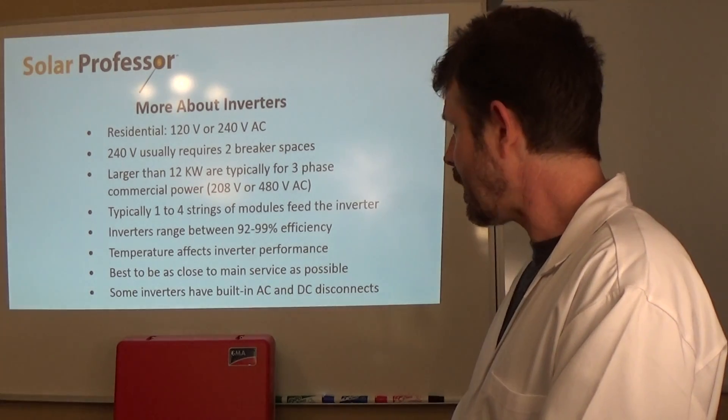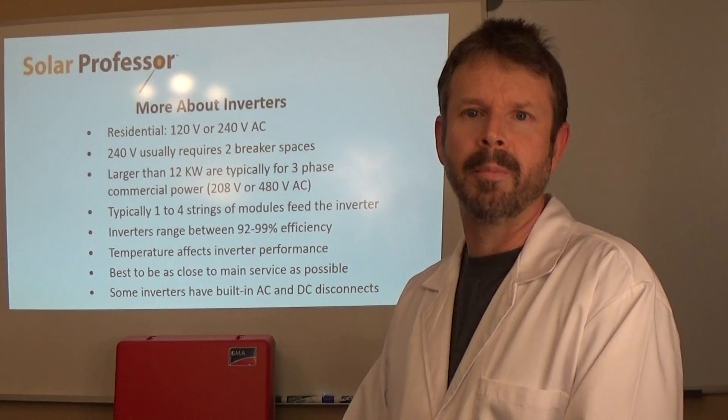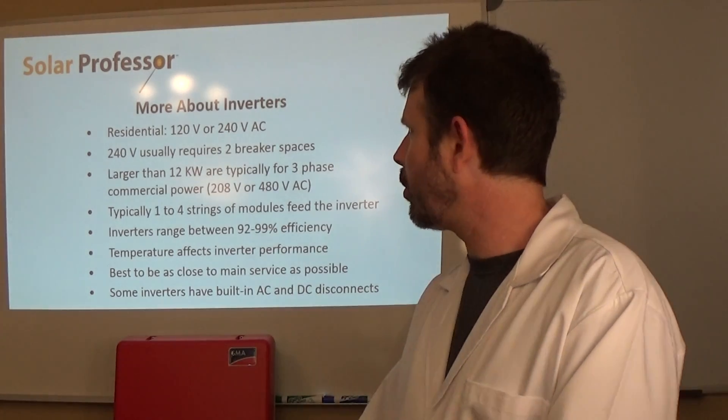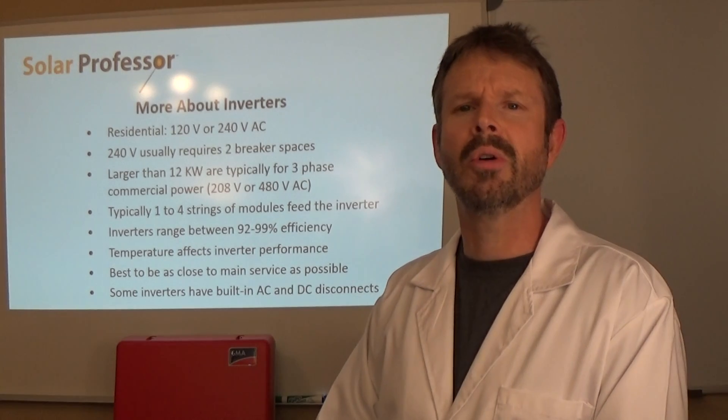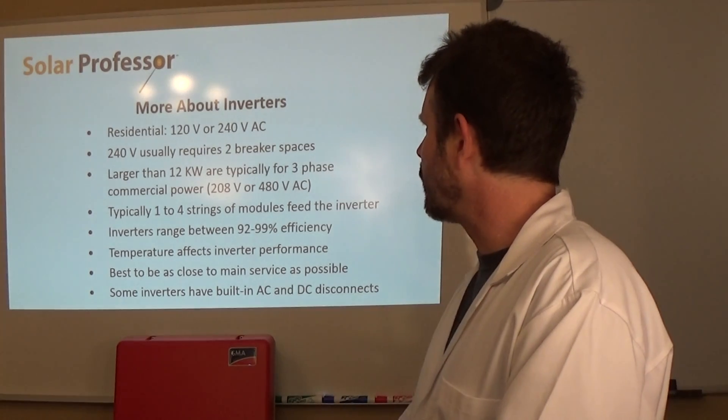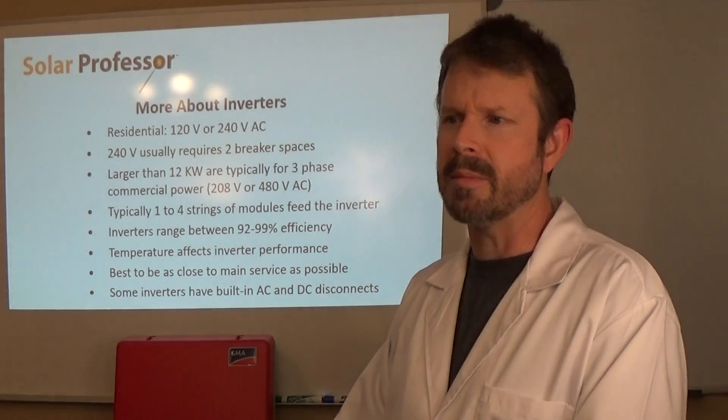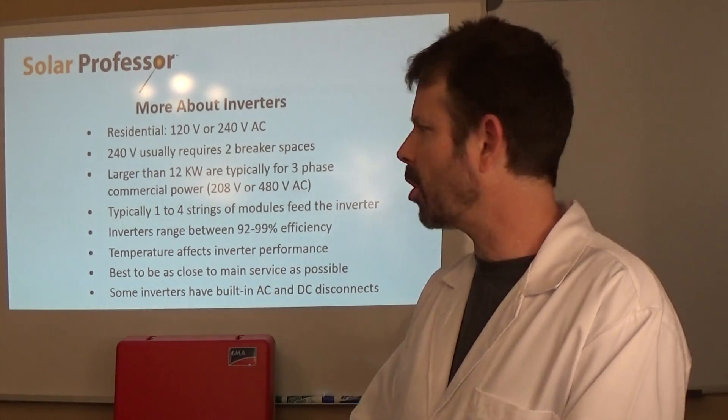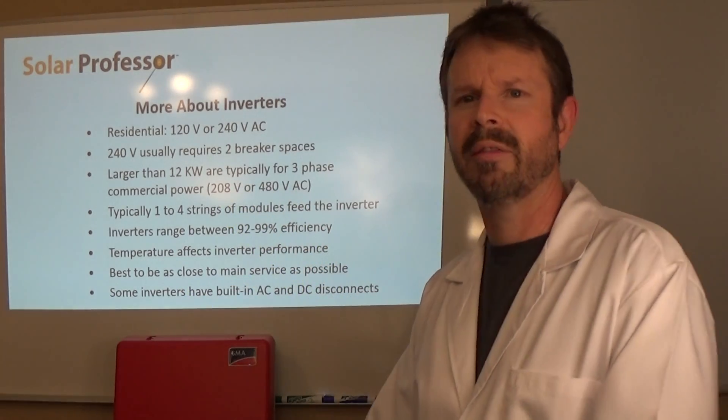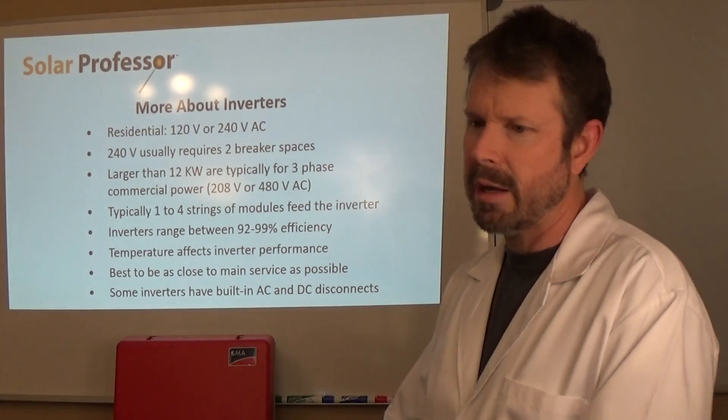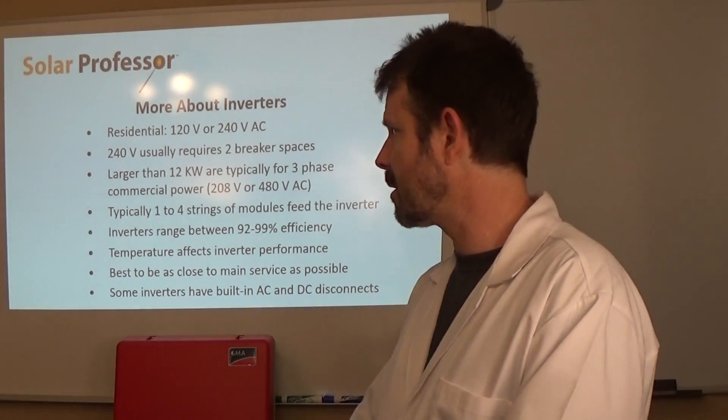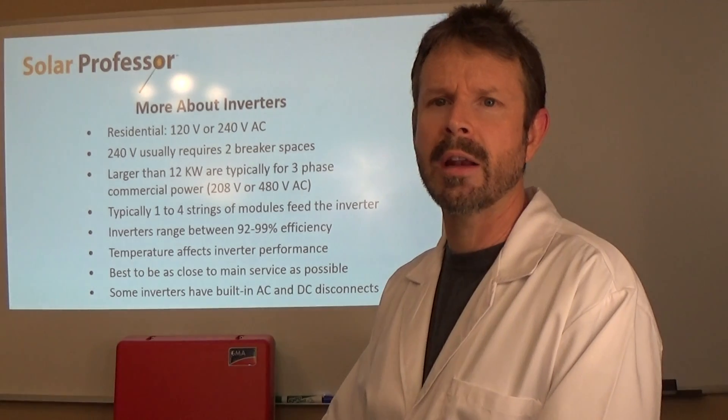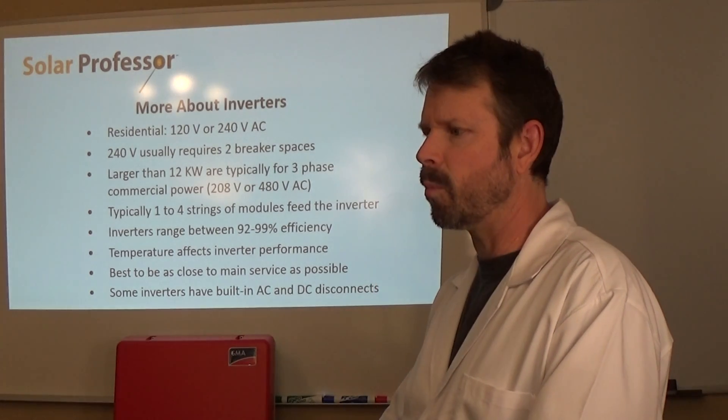More about inverters here. Residential inverters are either 120 volts or 240 volts. Most inverters are dual pole and they require two breaker spaces so that you can get 240 volts out of the inverter. Larger than 12 kilowatts are typically for commercial systems. You'll see 208, 480, sometimes 240 commercial three phase, sometimes 277. It depends on the equipment that you're using and the transformer that you're trying to connect the inverter to.